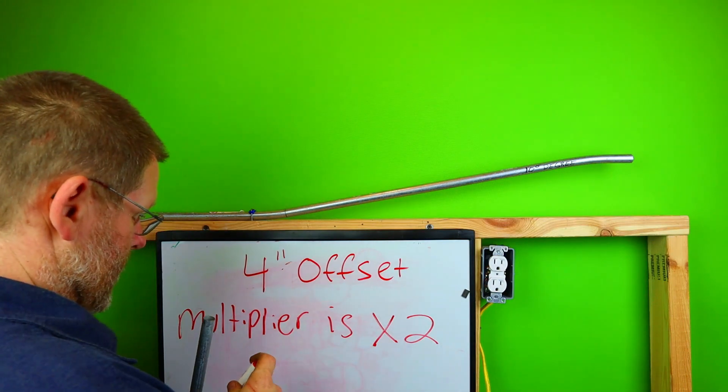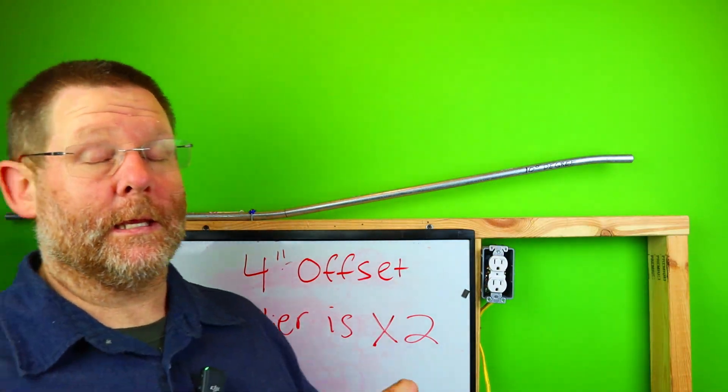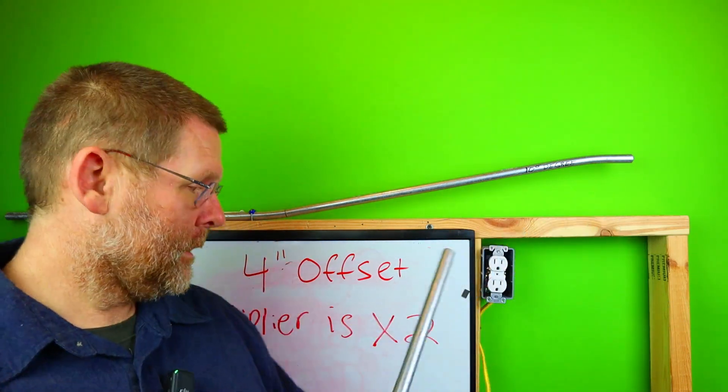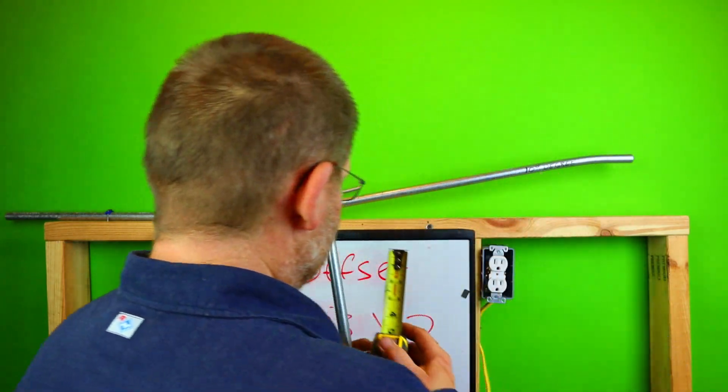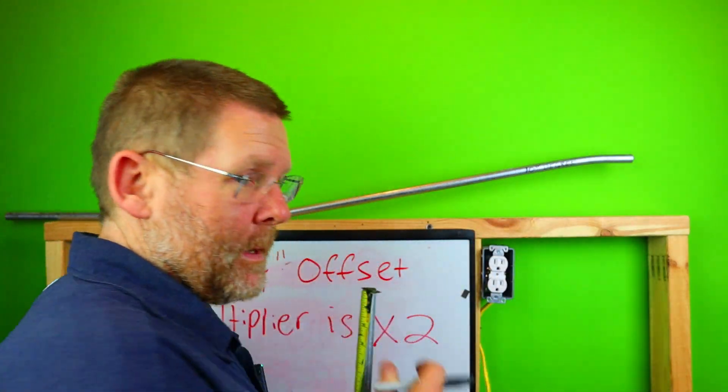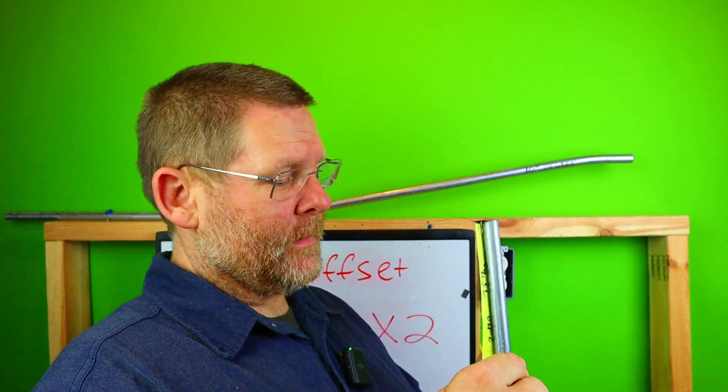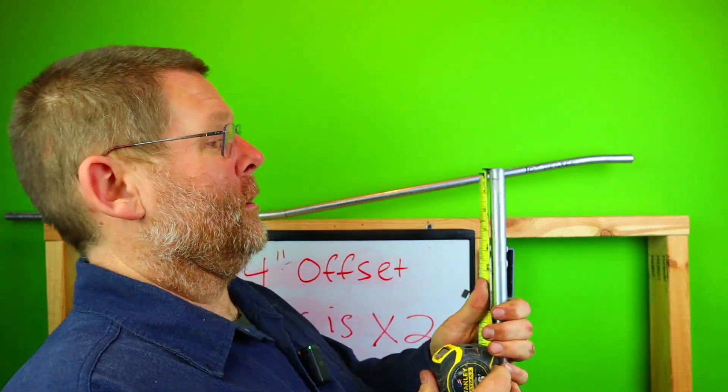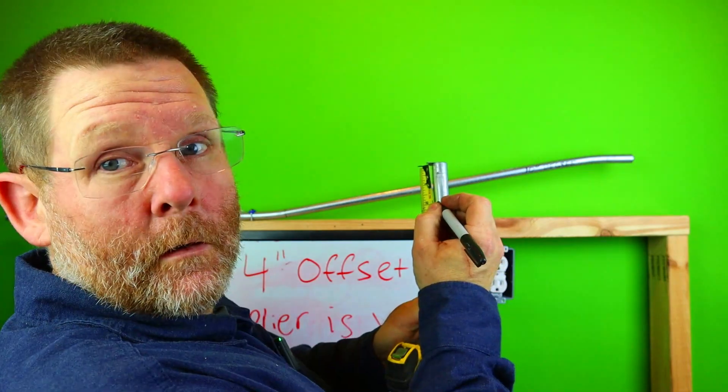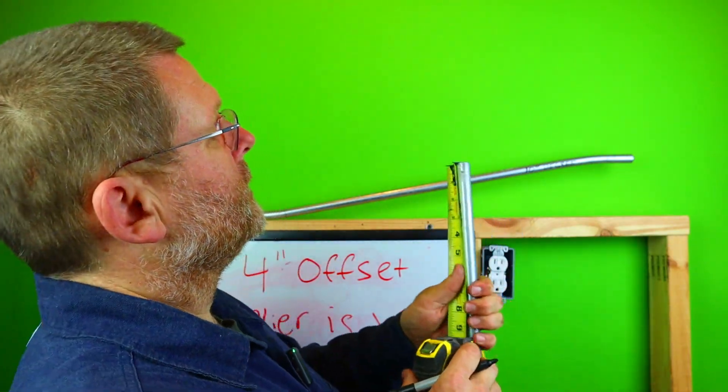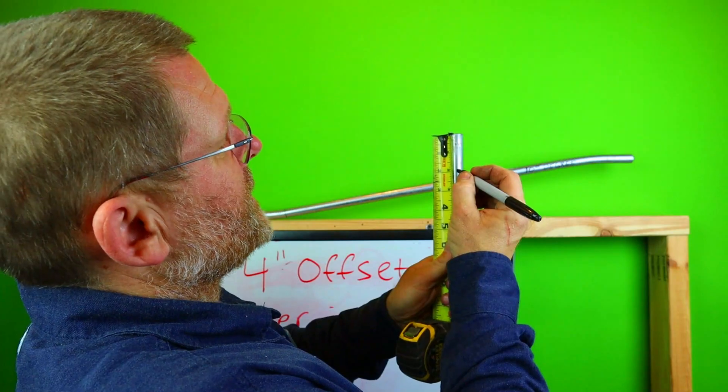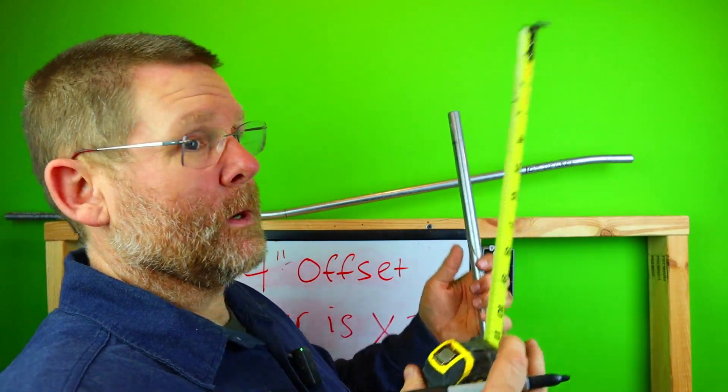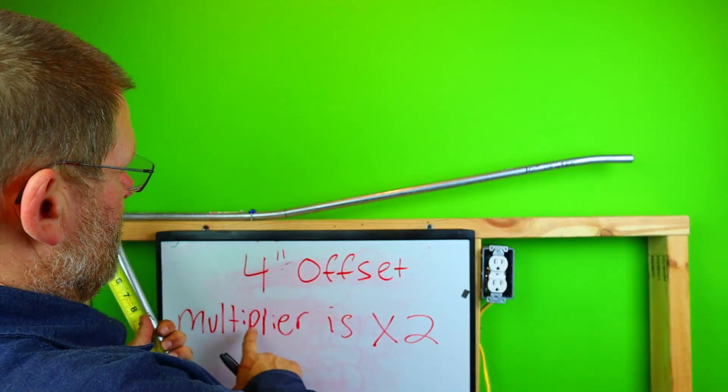So we know we need a 4-inch offset. 4 times 2 is 8. Can you remember back to last week when we saw the 22-degree bend? How much space was between the bends? While you're thinking about that, I'm gonna mark my first mark. Remember how far I come back on this pipe? I always come back two inches.